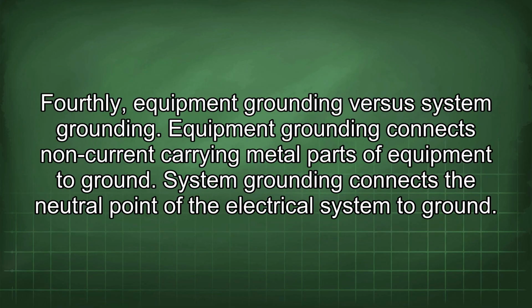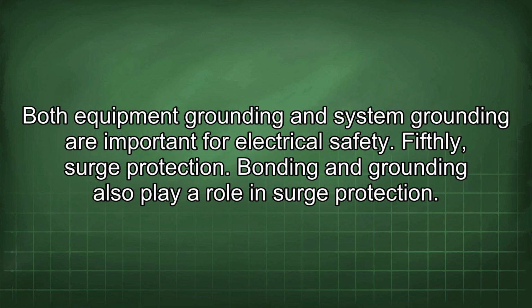Fourthly, equipment grounding versus system grounding. Equipment grounding connects non-current carrying metal parts of equipment to ground. System grounding connects the neutral point of the electrical system to ground. Both equipment grounding and system grounding are important for electrical safety.